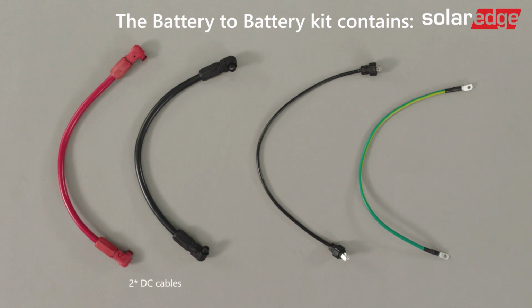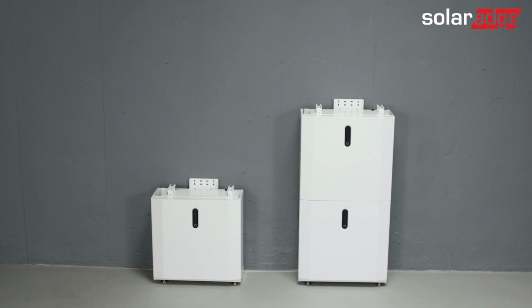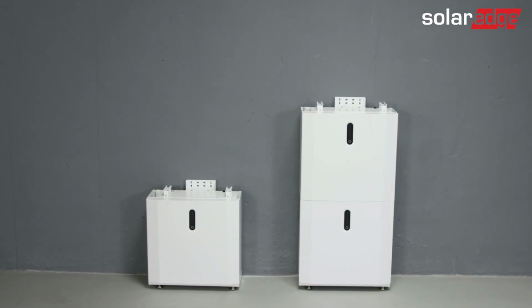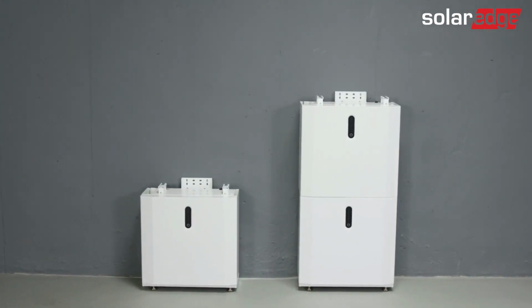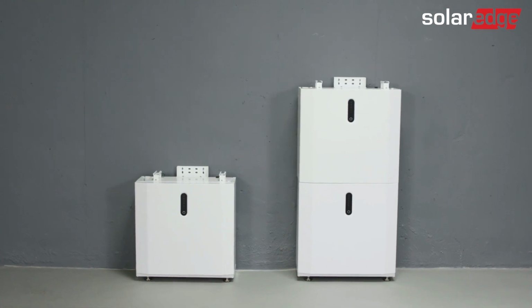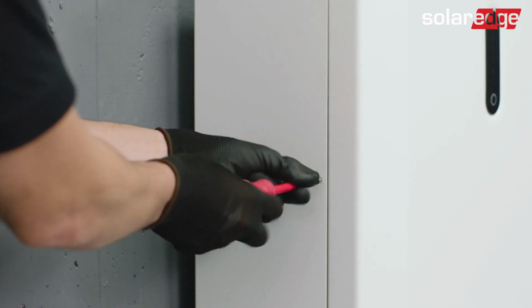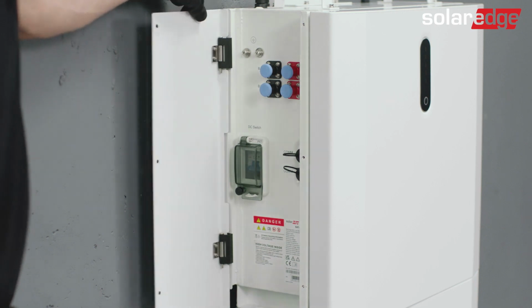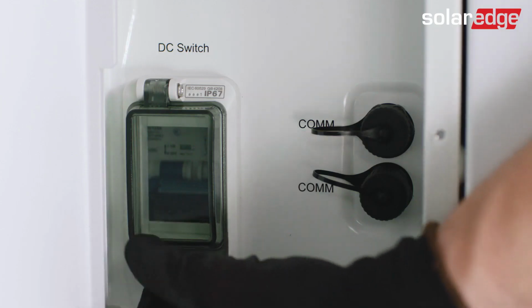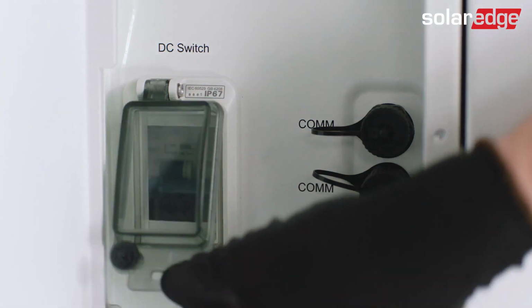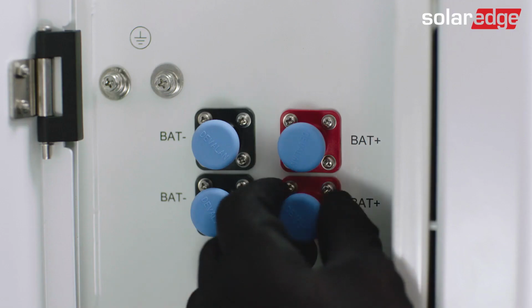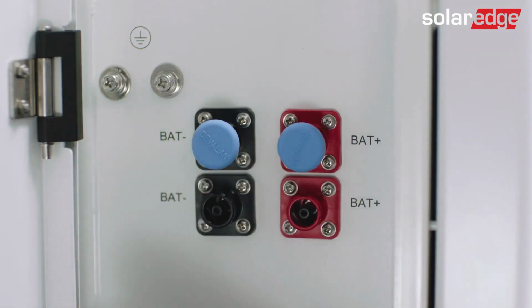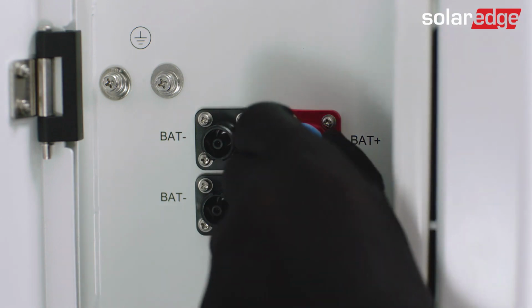In the battery-to-battery kit, you will find 2 DC cables, a communication cable, and a grounding cable. Please note additional cables and accessories should be ordered separately from SolarEdge, according to the amount of batteries you'd wish to install. First, open all of the left covers using the 3 screws. Before connecting any cable, make sure the circuit breakers are off in all the batteries. Then, pull the different plug-ins that are sealing the DC connectors and communication connections.